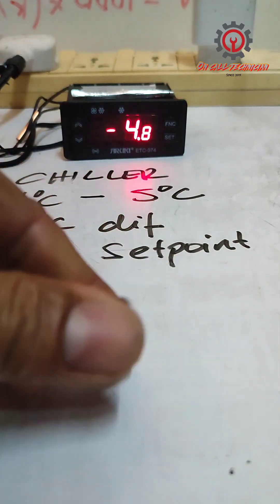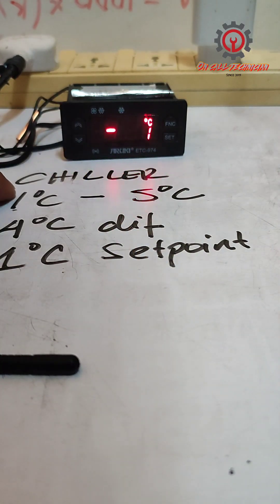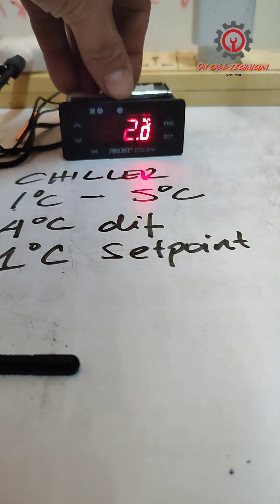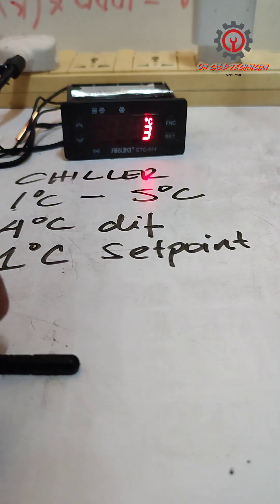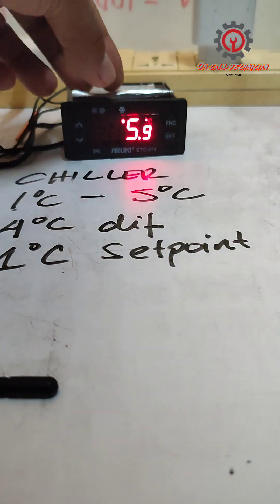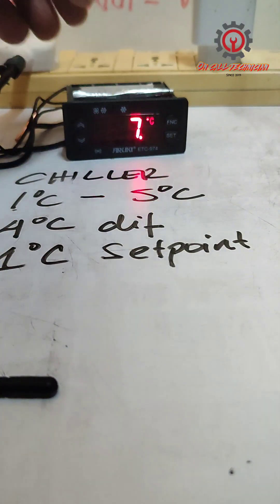Let's take a look. I'm holding the probe sensor. Once it reaches positive 5 here, the symbol light for the compressor will energize. There it is, it's now activated.